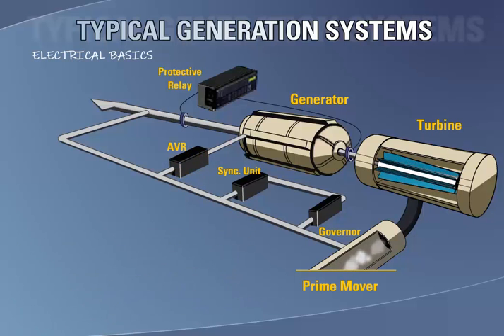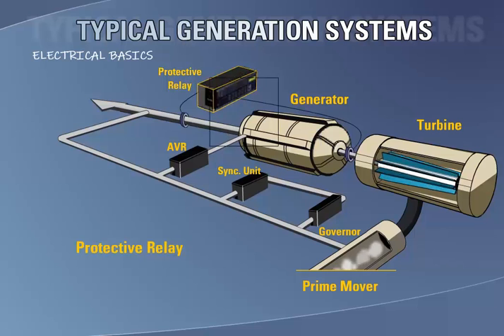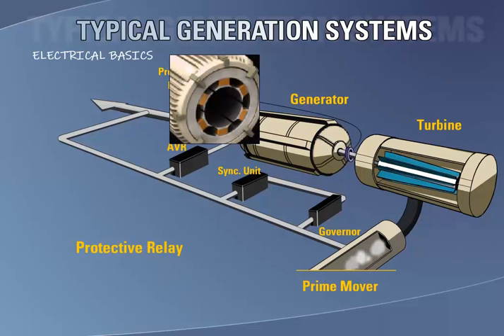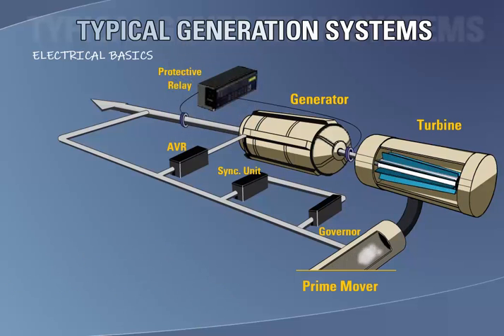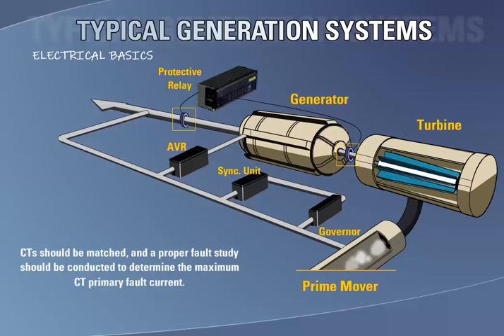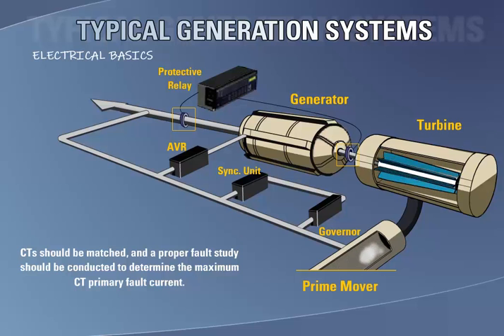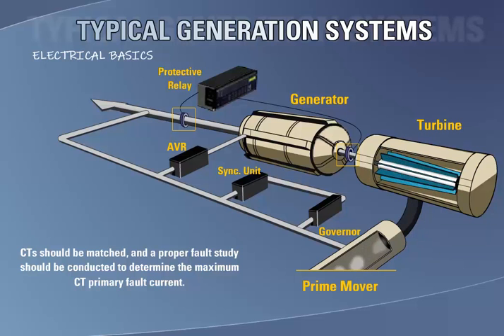The last of these three components is a protective relay. A relay will be connected to the generator stator circuit and will provide generator stator protection in addition to backup protection for the AVR and the governor. The correct selection of current transformers for the protective relay is an essential part of proper generator protection. The current transformers should be matched and a fault study conducted to determine the maximum CT primary fault current. With this information, the CTs chosen should be such that the maximum voltage at the CT secondary terminals at the time of the fault is less than 50% of the CT knee voltage.